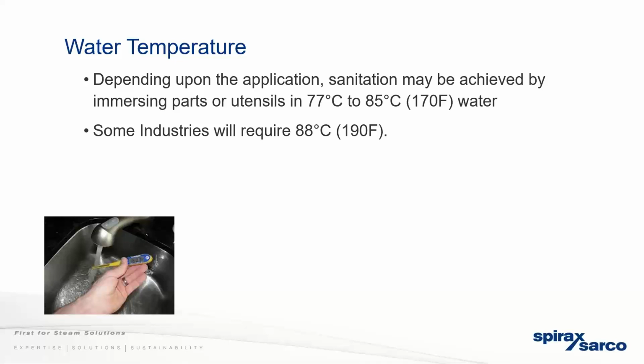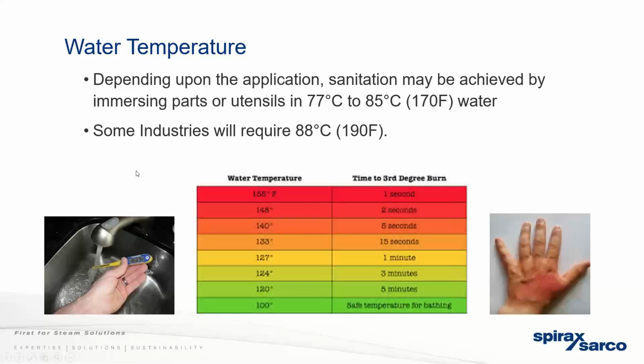Depending on the application, sanitation may be at 170 F or up to 190 F. You can see from this chart here, at 155 F, you can get burns within 1 second. So safety is important for food safety, but it's also important for employee safety. This should be considered when you're looking at different options for your washdown water heaters, to consider safety options.